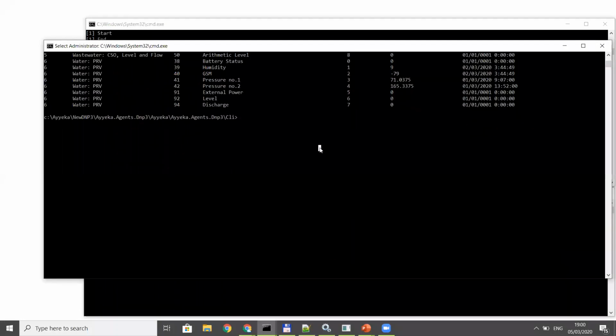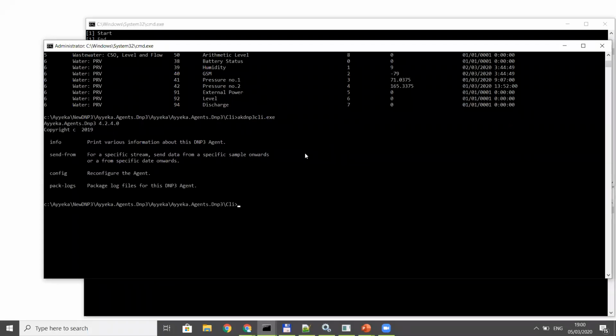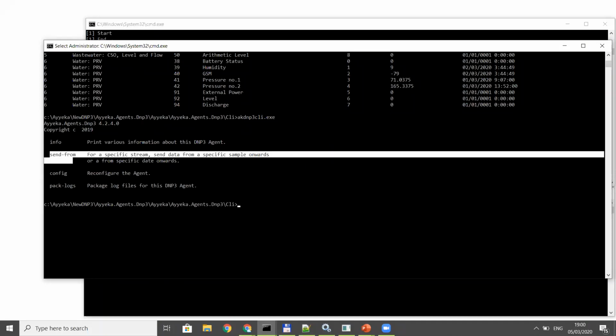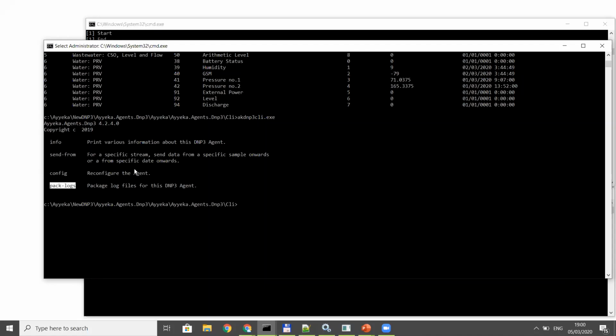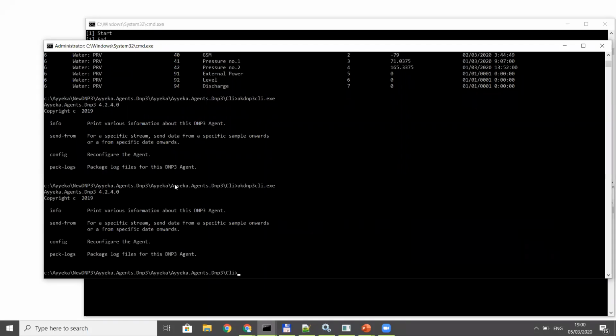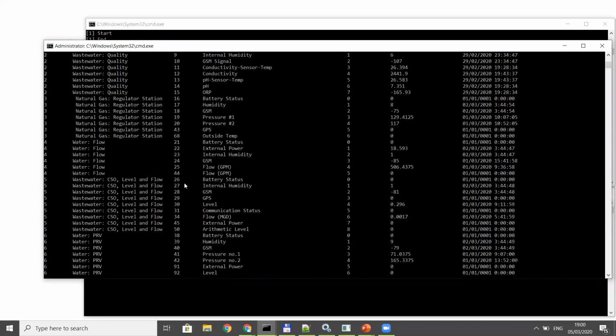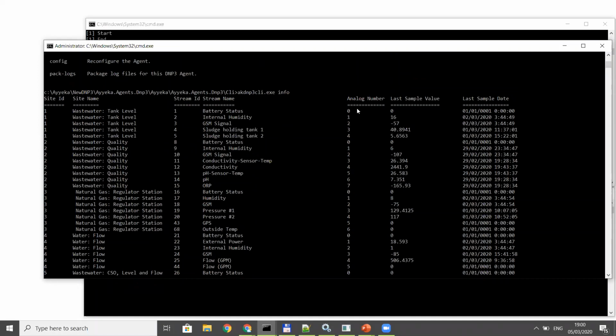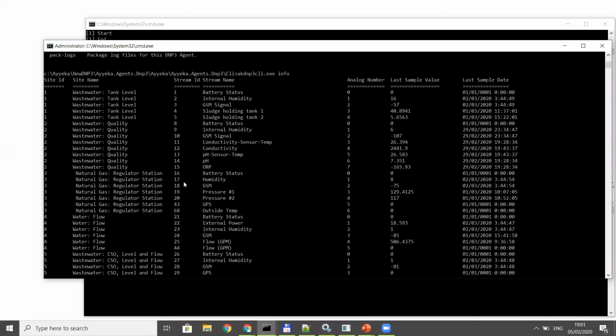First of all, we have a CLI for the DNP3, and it allows us to look at the info of the mapping as well as to reset the send dates and pack up logs for analysis. These are some of the utilities we provide for DNP3 integration. Here you can see if I do the info, it'll show a full mapping to all of the data, so here we can see what the streams are in our system and how they map into the SCADA system as analog channels.